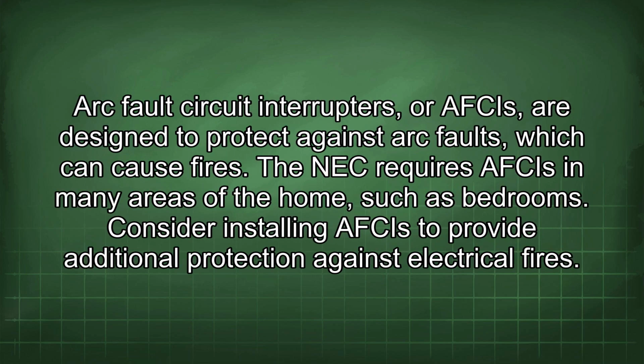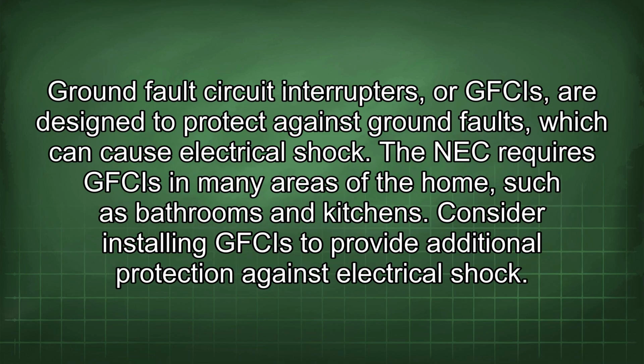Arc fault circuit interrupters, or AFCIs, are designed to protect against arc faults, which can cause fires. The NEC requires AFCIs in many areas of the home, such as bedrooms. Consider installing AFCIs to provide additional protection against electrical fires. Ground fault circuit interrupters, or GFCIs, are designed to protect against ground faults, which can cause electrical shock. The NEC requires GFCIs in many areas of a home, such as bathrooms and kitchens. Consider installing GFCIs to provide additional protection against electrical shock.